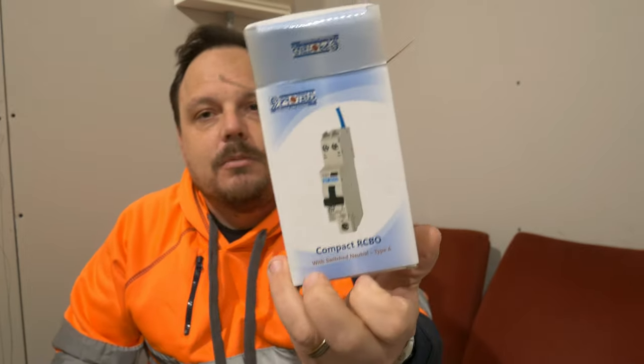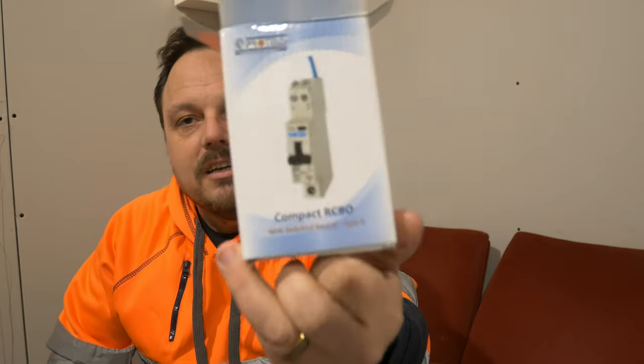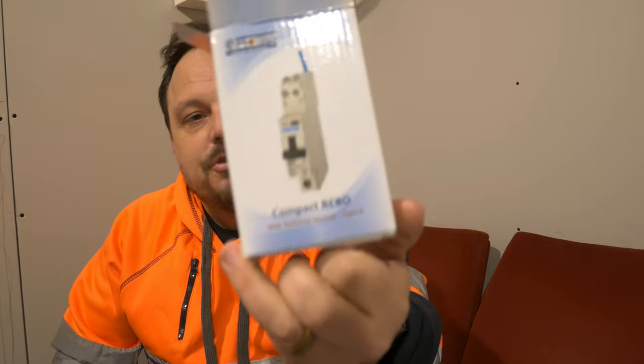Okay, so I did just want to have a quick look at the Proteus RCBO. Got it out of the box here. See, it comes in some cardboard packaging, no plastic inside it whatsoever, which is fantastic. Clearly states on the front that it's switch neutral. That's often a bugbear of installers, double pole switch neutral. What does it actually mean? And what application can we use them in? Typically we're concerned about that because of EVSEs and the need to open both line and neutral for us to satisfy the regulations in context of that application, and these do that.